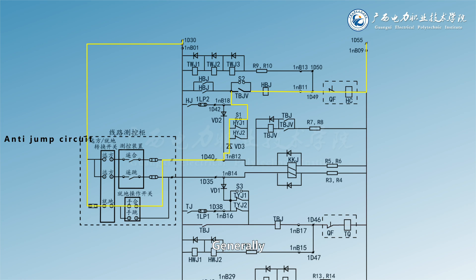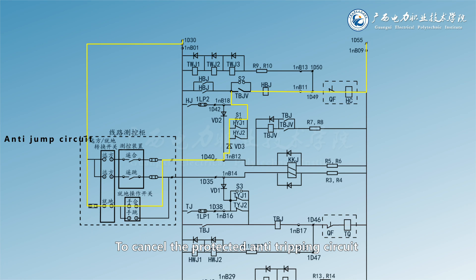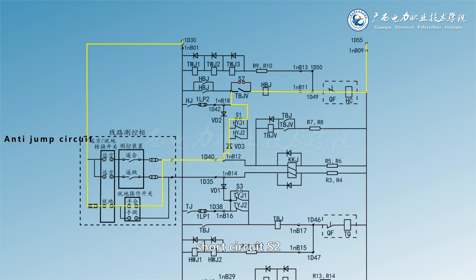Generally, the circuit breaker operating mechanism has its own anti-tripping circuit, while only one set of anti-tripping circuit can be used at a time. To cancel the protection's anti-tripping circuit and use the anti-tripping circuit of the circuit breaker itself, short circuit S2.